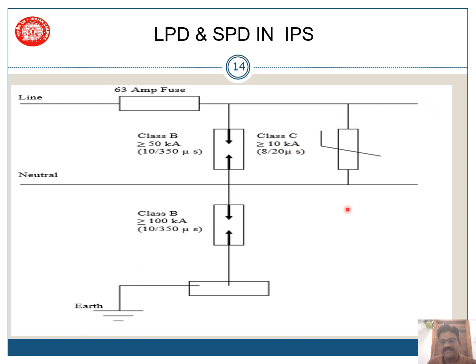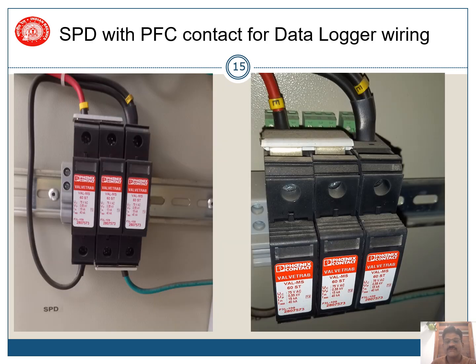If any voltage leaks through and reaches the IPS, then you have another range of protection, which is called class C protection, class D protection. So here you can see a simple example of SPDs. Here you can see the PFC contact, which can be connected to your data logger for remote monitoring also. Here you will get the red indication whenever there is any failure of your protection.